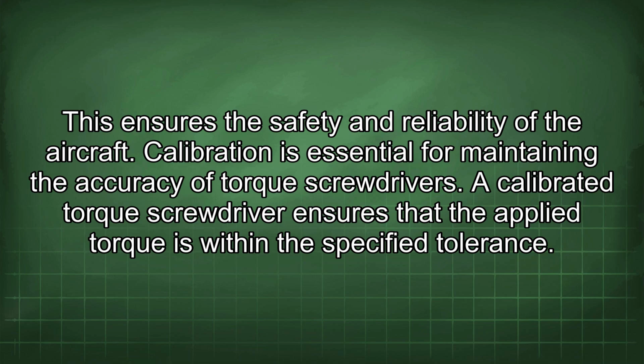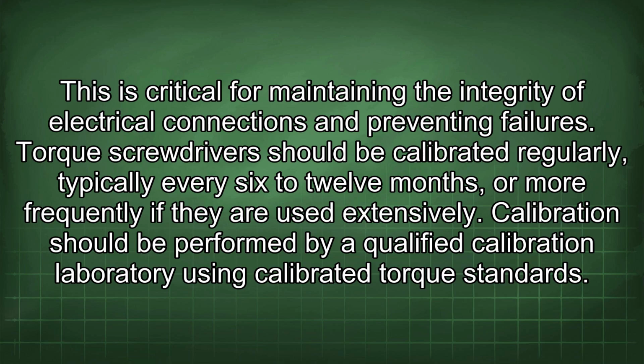Calibration is essential for maintaining the accuracy of torque screwdrivers. A calibrated torque screwdriver ensures that the applied torque is within the specified tolerance. This is critical for maintaining the integrity of electrical connections and preventing failures. Torque screwdrivers should be calibrated regularly, typically every 6 to 12 months, or more frequently if they are used extensively. Calibration should be performed by a qualified calibration laboratory using calibrated torque standards.